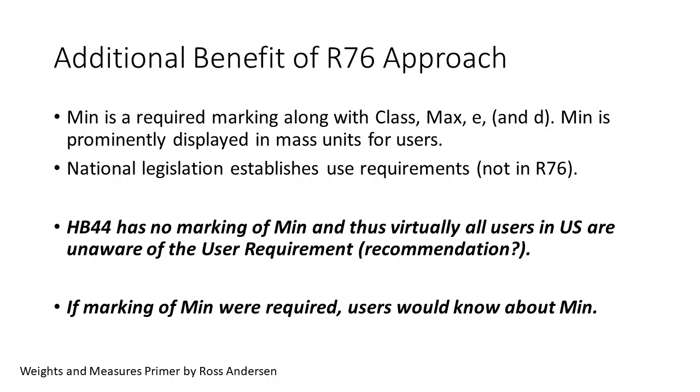Handbook 44 requires no marking of min, and thus virtually all users in the U.S. are unaware that an instrument has a lower limit. The marking would become part of the manufacturer's specifications, impacting the instrument selection, and every user would see the minimum load on the face of the instrument.